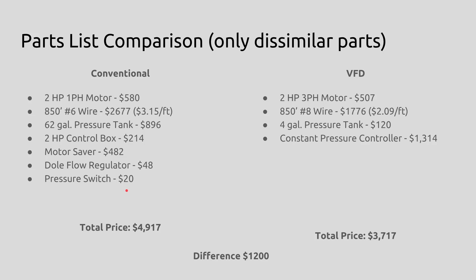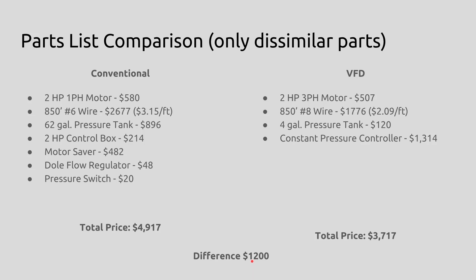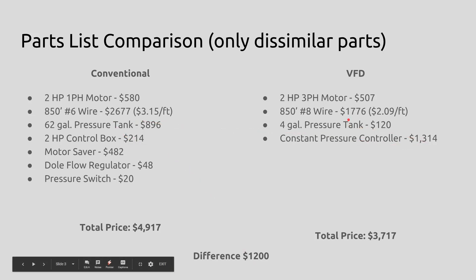The pressure switch is a part that's not in a VFD system as well. So the total difference in parts is $1,200. The total price is $4,917 versus $3,717 — this is only the dissimilar parts. So the difference is in favor of the VFD in this situation by $1,200. That wire definitely added up quite a bit here: $2,600 versus $1,700.